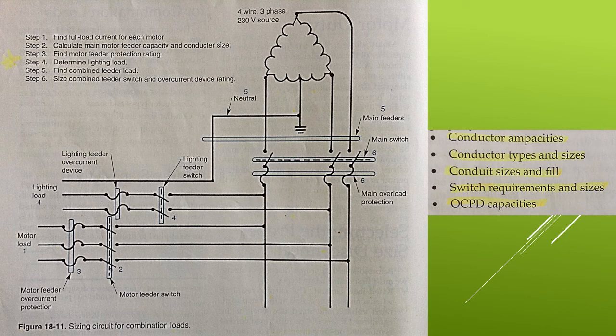Sizing circuit components for combination loads. The circuit shown in figure 18-11 includes two 1.5 horsepower, one 7.5 horsepower, and one 10 horsepower squirrel cage motors plus a lighting load of 26,000 VA. The supply consists of a 4-wire, 3-phase, 230-volt delta transformer. In order to properly install this circuit, we must determine, as shown on the right side of the screen, conductor ampacities, conductor types and sizes, conduit sizes and fill, switch requirements and sizes, and OCPD capacities.